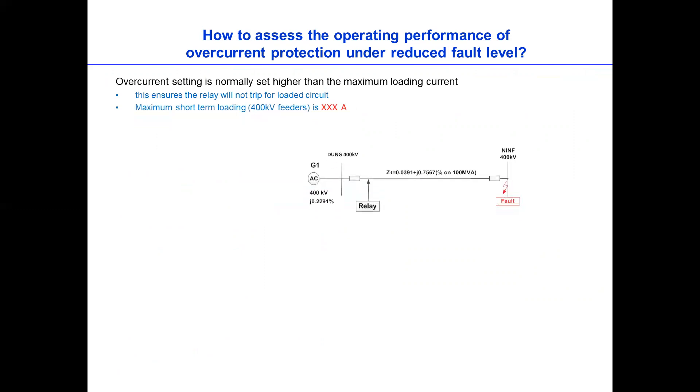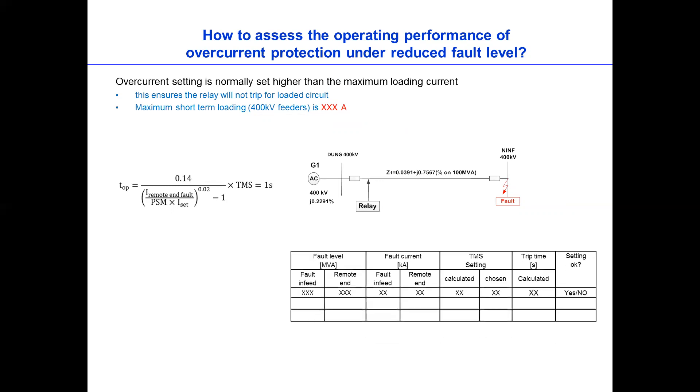And the next section is how to assess the operating performance of overcurrent protection under reduced fault level. Well, this is a hot topic at the moment because of the penetration of renewable energy sources. So the fault level is reduced substantially, as we are using low inertia technology. So the problem or the challenge is how do we set overcurrent protection as compared to conventional.